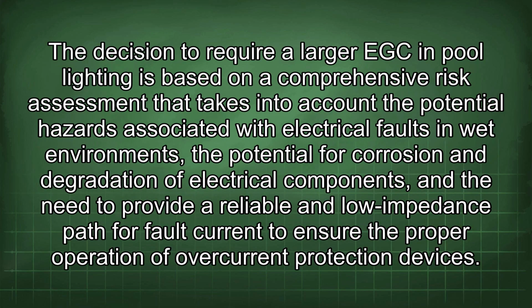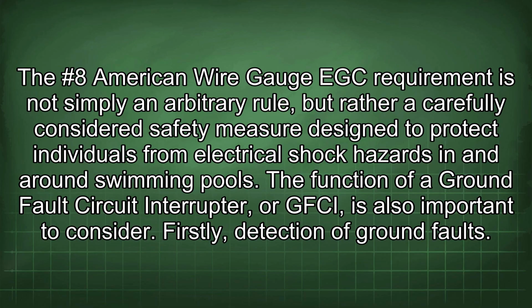The decision to require a larger EGC in pool lighting is based on a comprehensive risk assessment that takes into account the potential hazards associated with electrical faults in wet environments, the potential for corrosion and degradation of electrical components, and the need to provide a reliable and low-impedance path for fault current to ensure the proper operation of overcurrent protection devices. The #8 American wire gauge EGC requirement is not simply an arbitrary rule, but rather a carefully considered safety measure designed to protect individuals from electrical shock hazards in and around swimming pools.